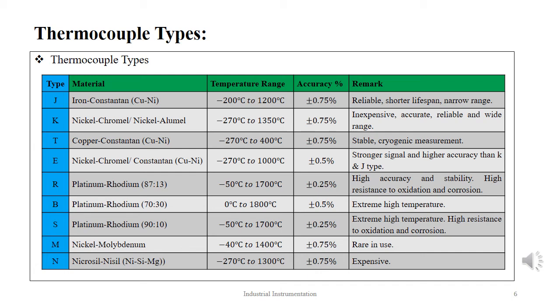We see here that the best accuracy is provided by the R and the S type thermocouples, both of which are made up of platinum and rhodium. The B type thermocouple has the highest temperature measurement range, while the K, T, E, and N type thermocouples can measure very low temperatures as low as minus 270 degrees Celsius. Based on the percentage composition, the platinum rhodium thermocouples are of 3 types, which are R, B, and S types. Iron, copper, and nickel chromium couple with constantan, that is an alloy of copper and nickel, form the J, T, and E type thermocouples respectively.